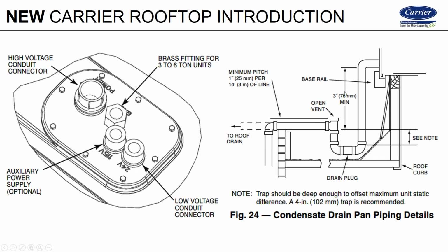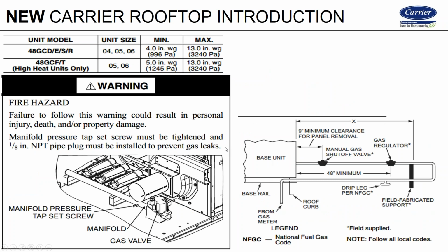Our traps, 3-inch minimum plus 1 inch for every additional inch of static. So if you have an inch of static, I would take 1 inch plus that 3-inch, you'd have a 4-inch deep trap. If you had a unit with 2 inches of external static, I'd add 2 inches to the 3-inch dimension. So nothing's changed on these units. That all works the same way. They do need to be vented. So pretty simple there.